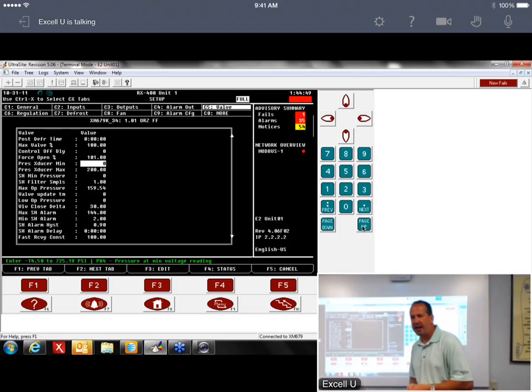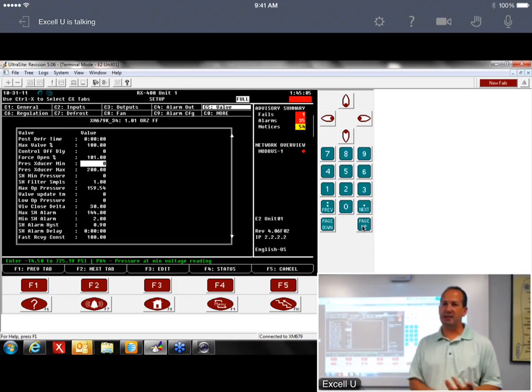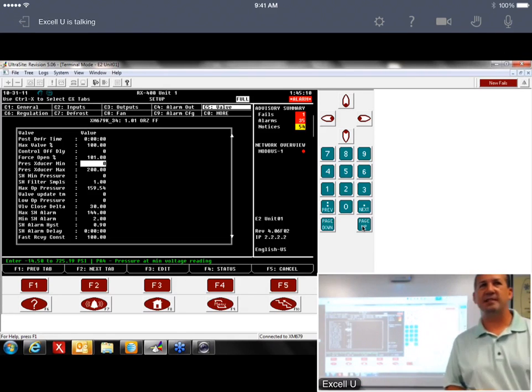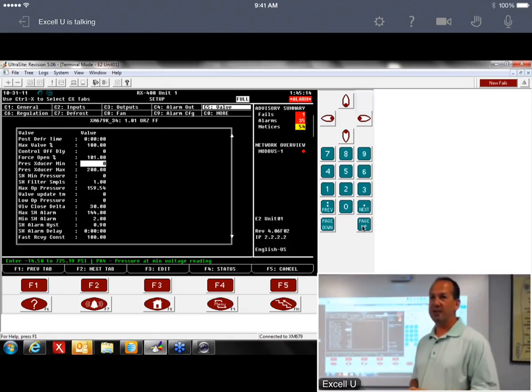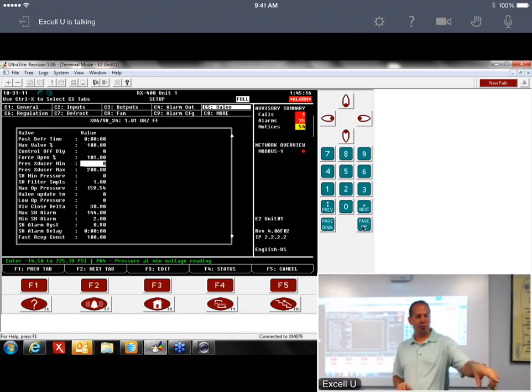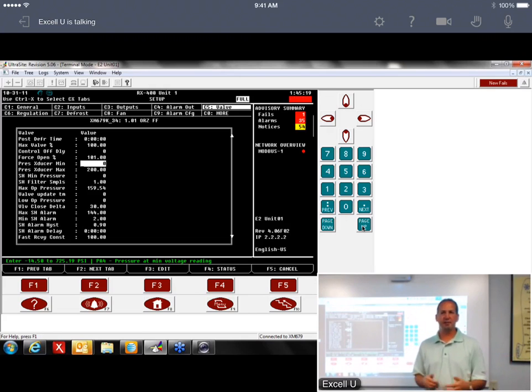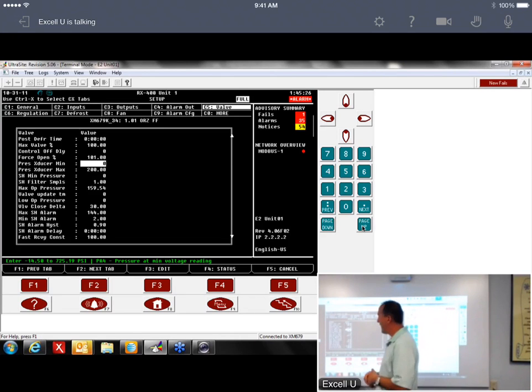If you've got a system that's just not acting right, and it's acting screwy and nothing's really working the way it should, one thing I would check, I would come into this tab and look at these two parameters. And if you see -7 for the min and 160 for the max, then the parameters that were in this device when it shipped got put into your E2. That's a telltale sign, because it's set up for some funky transducer they use in Italy or something, I don't know. But anyway, the default parameter in that device for Transducer Max Min is -7 and 160.